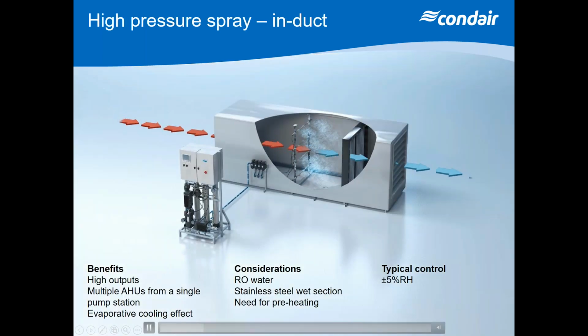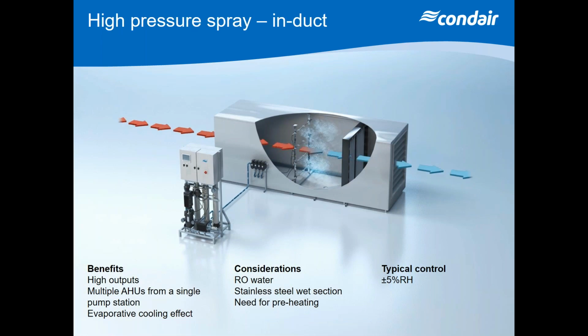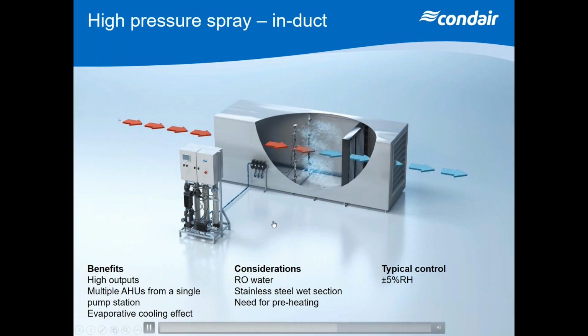If I want to do better than that, I would go to a high pressure system. So different system here completely. So with a high pressure system, we go through an RO plant, we take the minerals out of the water, and we then pump that RO water at high pressure to a spray manifold bar with a series of nozzles mounted on the bars. And when we get a varying demand signal, we will turn on or off certain nozzles or certain bars on this manifold. And by doing that, I can get plus or minus 5% RH control.